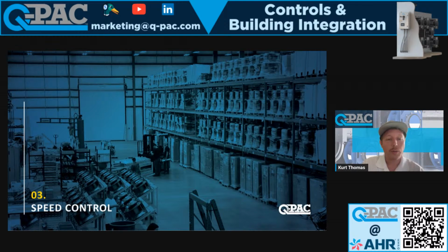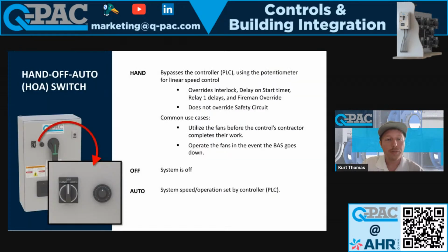All right, so in order to control the speed of your fans, we have several options. At the very front of your control panel, like I mentioned, you have an HOA switch. You have hand, off, and auto. Off is exactly as it sounds. Your system's not going to run. Your fans are not going to turn. It can still have power. You can still communicate to it via BACnet. The BACnet is just going to tell you that your fans are off.